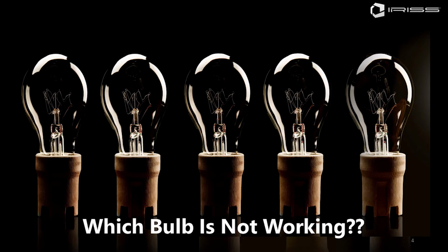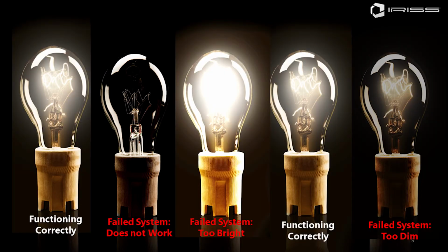The challenge with electrical systems is that I can't tell if it's working properly when it's off, right? Which one of these light bulbs might be defective? Don't know. I've got no way of testing necessarily that light bulb. Well, okay, maybe I could do a resistance test on it or something like that. But for the most part, our electrical assets, it's very difficult to tell what's happening unless we energize them. All or most of our condition-based techniques that we deploy to assess the health of our electrical assets require those assets to be energized at the time that we're performing the test.